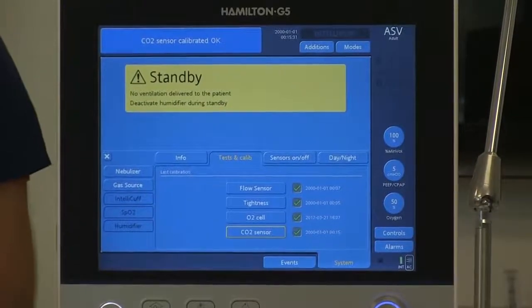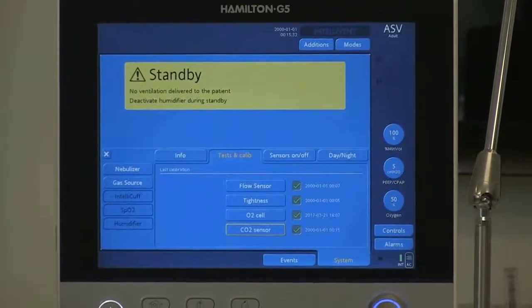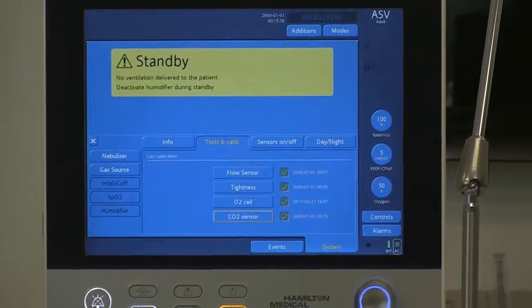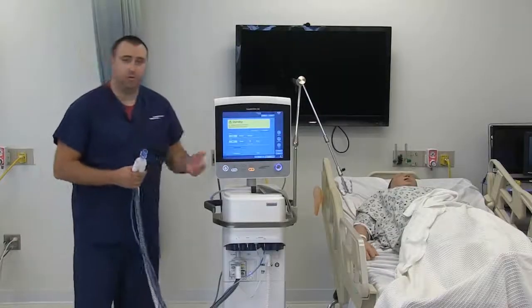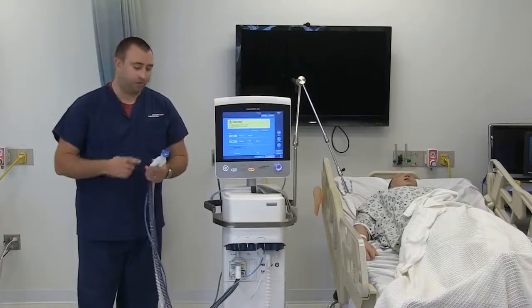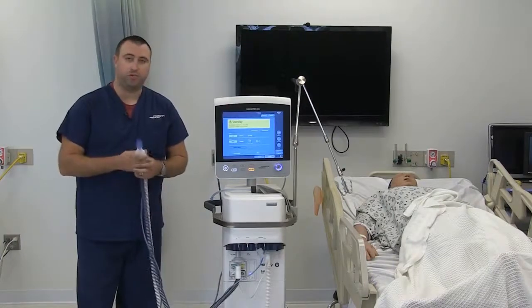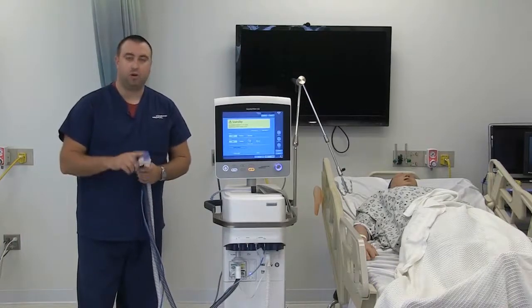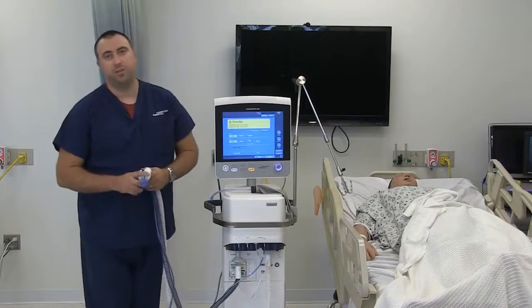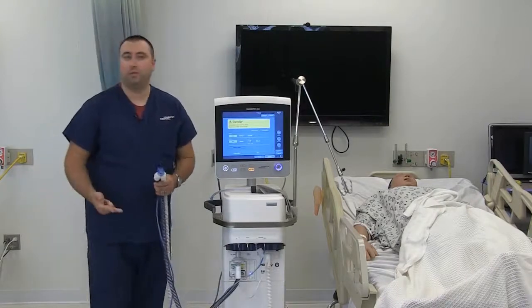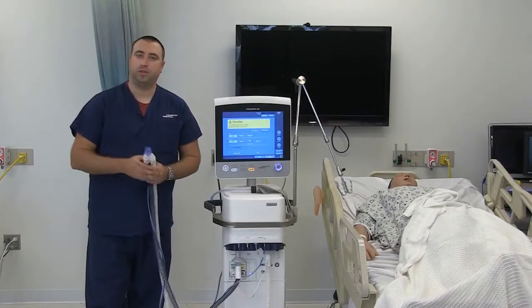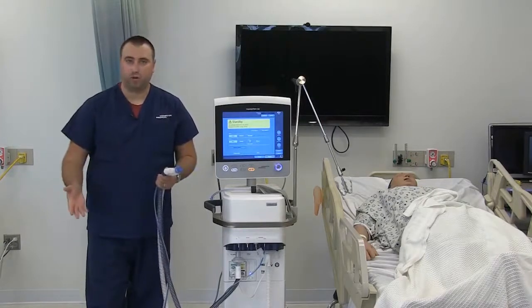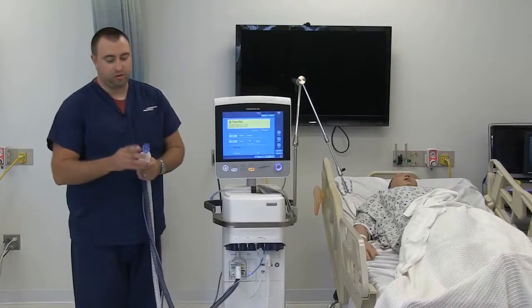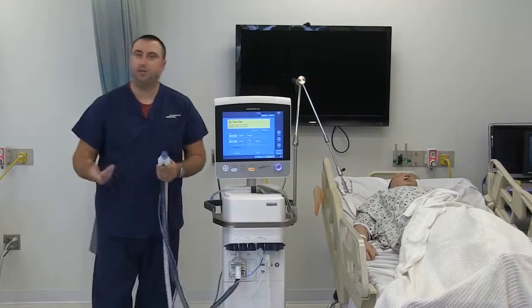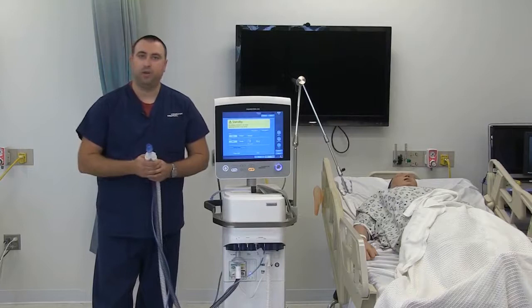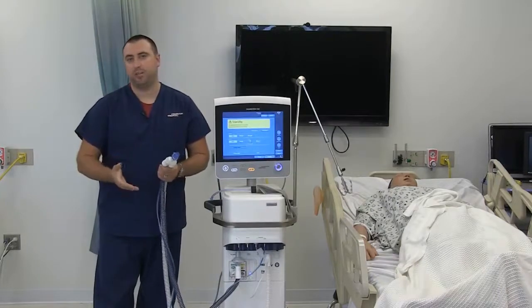CO2 sensor calibrated, OK. Now you're ready to place the CO2 on the patient. Before I get into the actual usage and demonstration of the G5, I would first like to talk about the proximal flow sensor. The proximal flow sensor on Hamilton products measures not only volume, but pressure and flow, making it a unique flow sensor in the ventilation world. Because of this, we're able to get advanced data that you would normally need advanced maneuvers to get, such as static compliance, breath by breath.